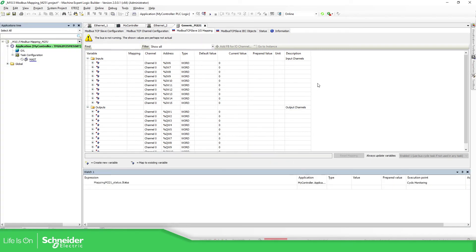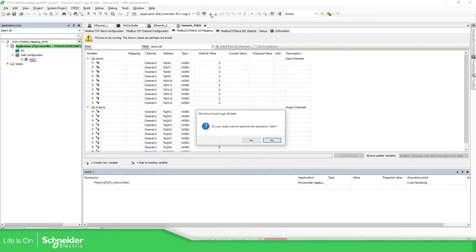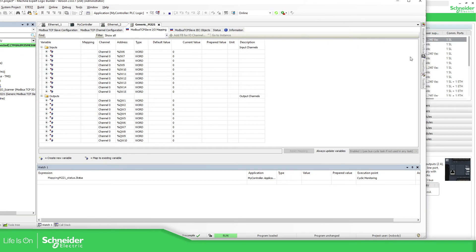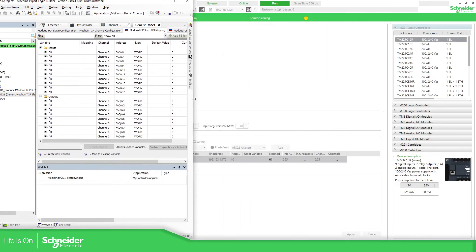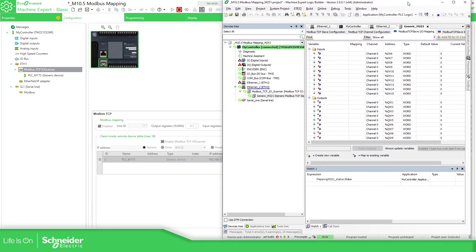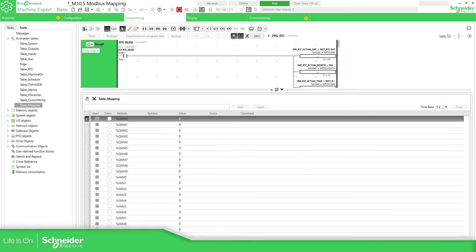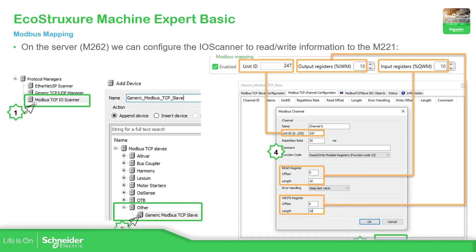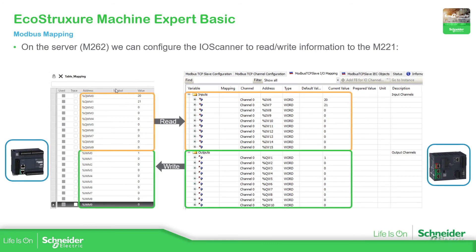The PLC was in stop, now I'm going to run it. If you go to the device tree, you can see that the communication with the device is correct and we can see some information. Going back to the slide, I want to show you the read and write area for the PLC. The output for the M262 would be the input from the M221 side — that's the IWM — and the reading for the M262 would be the output from the M221.